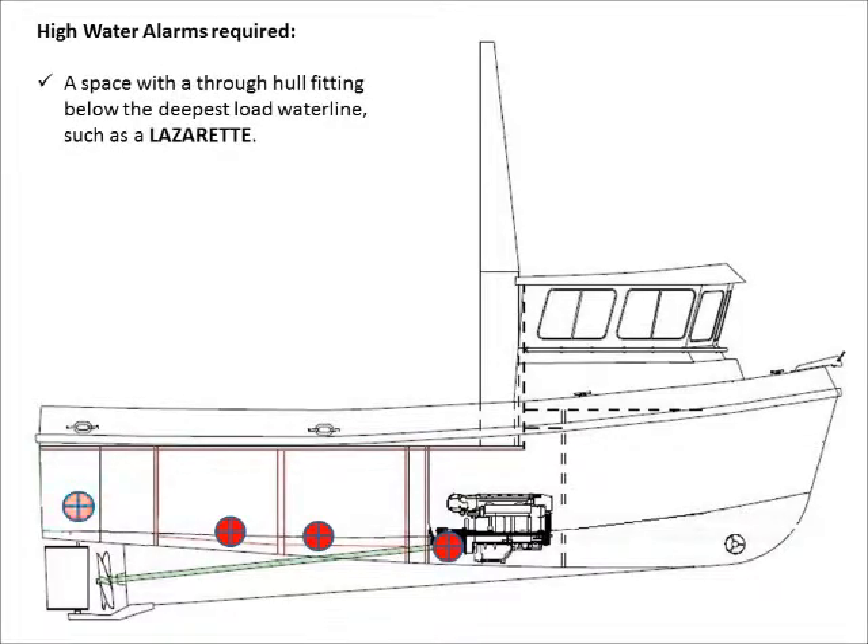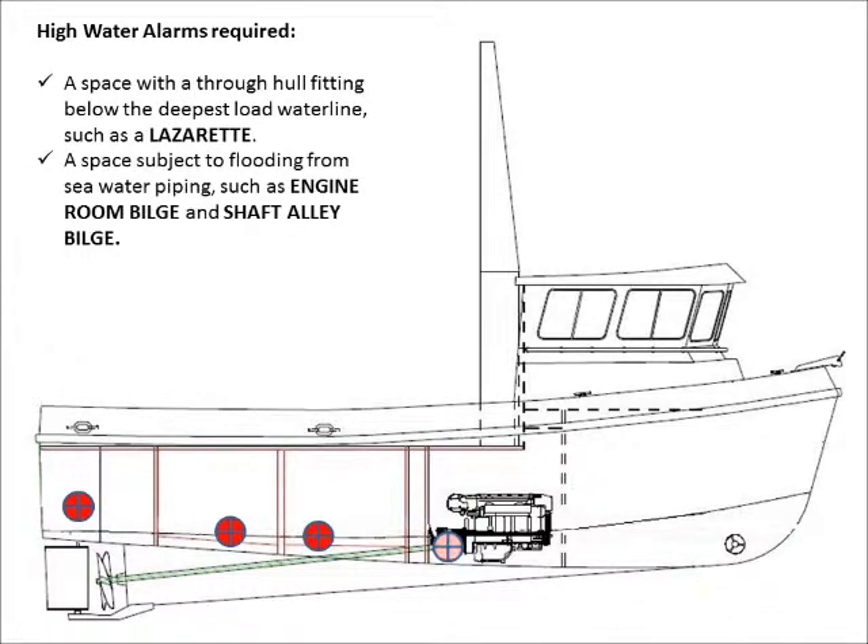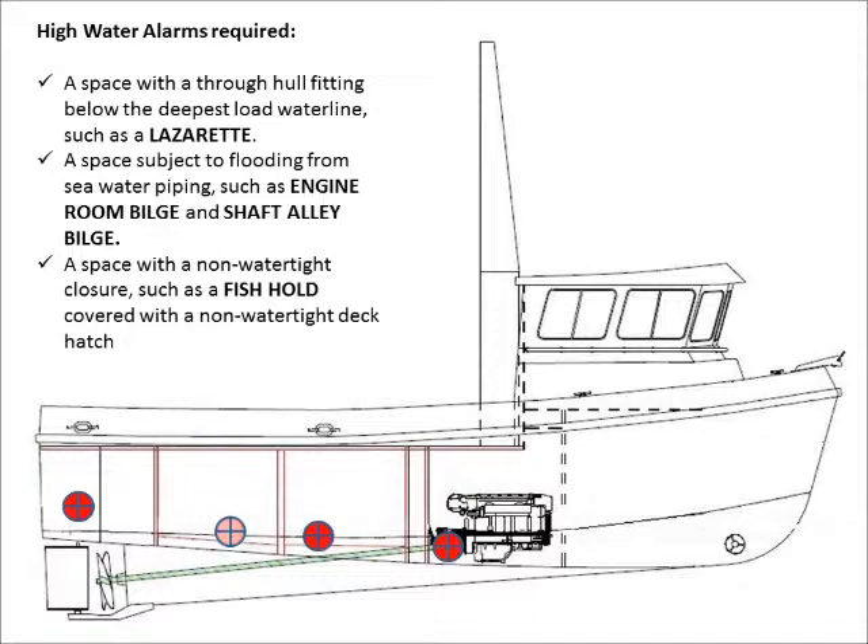A high-water alarm is required in a space with a through-hull fitting below the deepest load water line, such as the lazarette; a space subject to flooding from sea water piping, such as the engine room bilge and a shaft alley bilge; or a space with a non-watertight closure, such as a fish hold covered with a non-watertight deck hatch.